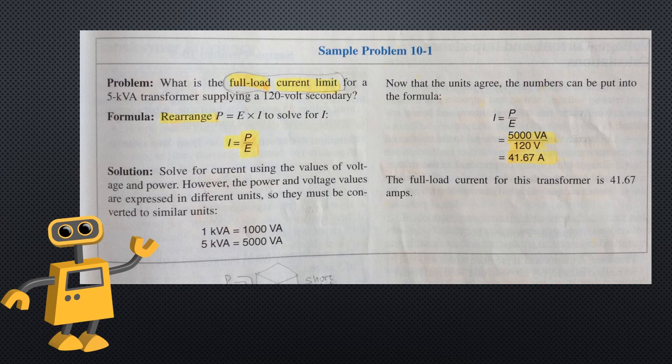Sample problem 10-1: What is the full load current limit for a 5 kVA transformer supplying a 120 volt secondary? Rearrange P = E × I to solve for current: I = P ÷ E. Convert 5 kVA to 5000 VA so units agree. Then divide 5000 VA by 120 volts to get 41.67 amps. The full load current for this transformer is 41.67 amps.